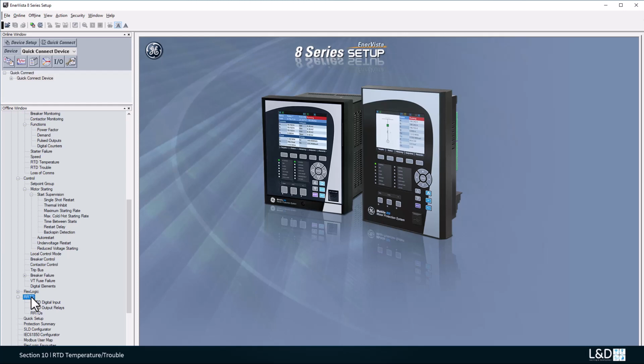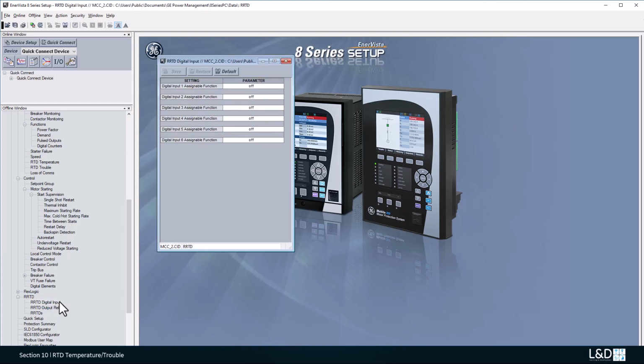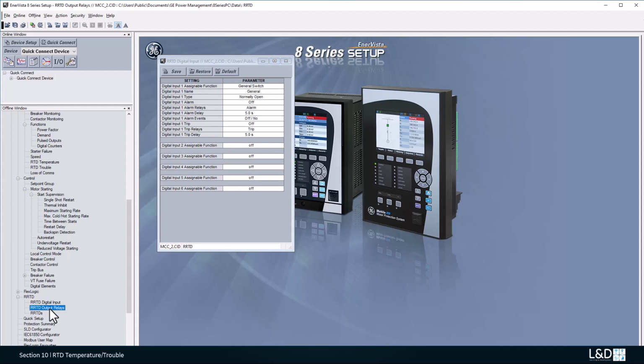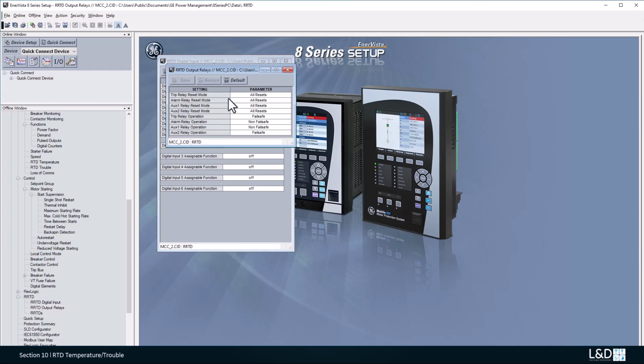The RRTD modules have been designed to be mounted closer to the motor to reduce the length of the RTD cables. The 859 can then monitor the RTD from a remote location and use this temperature information for protection and metering purposes. Each remote RTD module supports 6 digital inputs, and each one can be assigned to the general switch or the digital counter. It also supports 4 output relays.